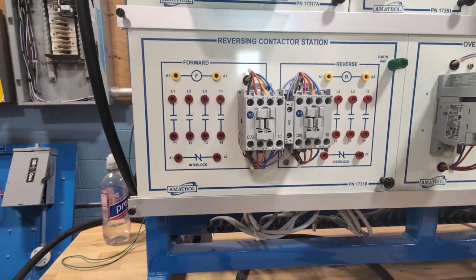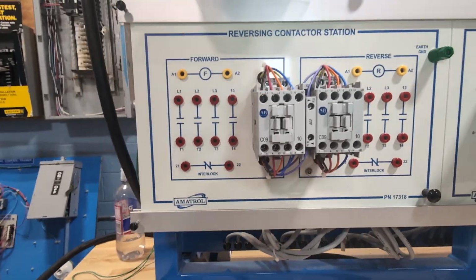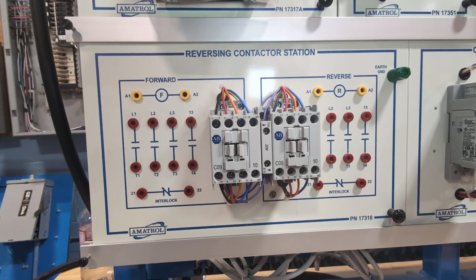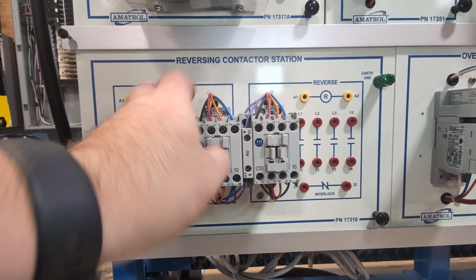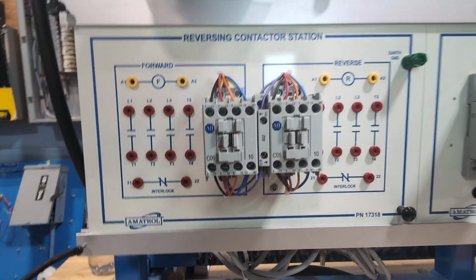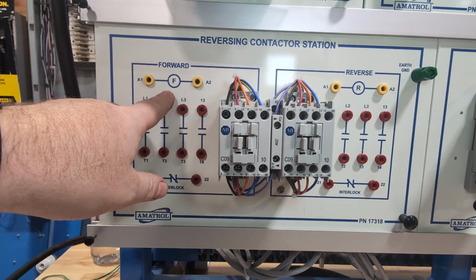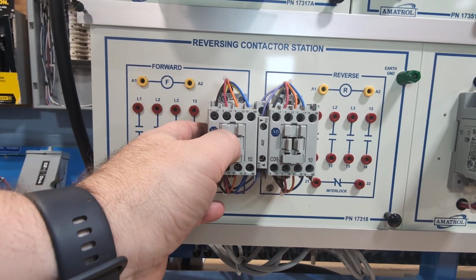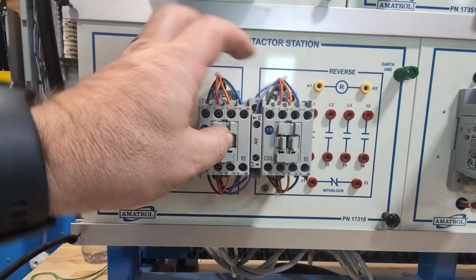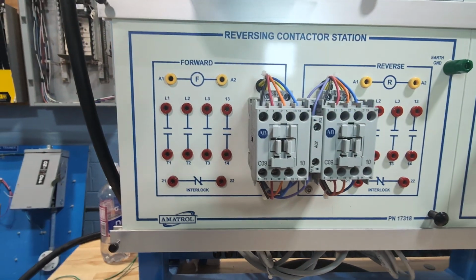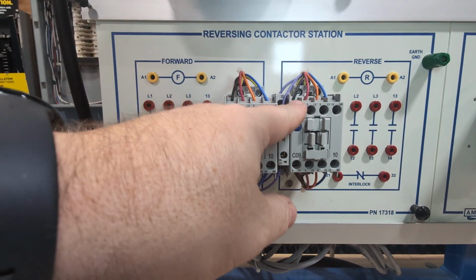Now, this is called the meat and potatoes of the motor. It's called forward and reverse coils contactors. Forward, reverse. Same thing as above there. I have my coil internal here, a magnet. It pushes it in. As it pushes in, this can't pull. It's interlocked. Can't push that in. That is called a start, forward, reverse.